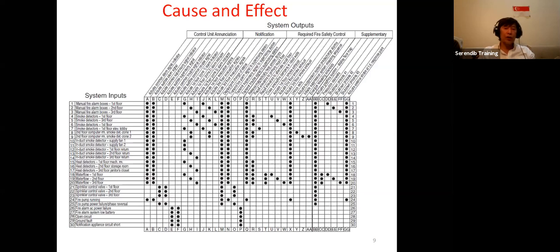But if we go along with NFPA 2001, which makes reference to NFPA 72, pertaining to detection alone, there isn't any discussion about first knock, second knock, cross zone, whatever. It is kept open. If you want to do it that way, go ahead.